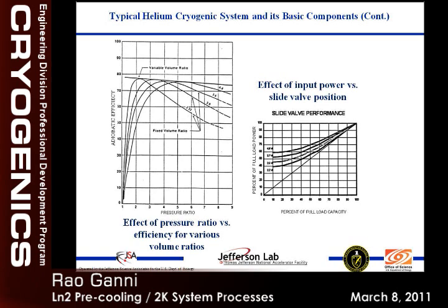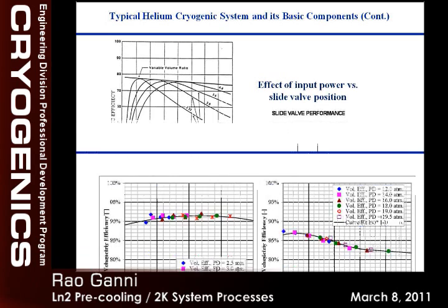These are all collected on Freon or air and not on the helium. They are a lot worse than these on the helium service. That's why we don't use any of these. Basically, we try to match a built-in volume ratio, which is ideal, and we'll go into that. And then we let the floating pressure determine it so that the pressure ratio is always staying, and we don't have to really worry about these unnecessary details and headaches in a floating pressure.